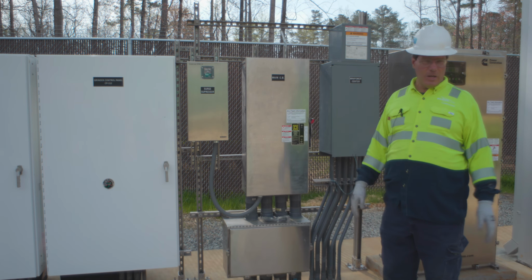And I'll demonstrate. So if I put this in hand, nothing happens because the PLC holds out the, oh wait. So okay, that's not the case here then. What's that? Most of them, the hand overrides it. All right. Well, in some places the PLC holds that out too, but in any case, the only thing that's held out then is the float controls. So some of the older stations, the hand-off-auto switch is also held out, but in this case it's only the float controls. So you can run these in hand when you turn it to hand, and when it's in auto, it's in PLC control.